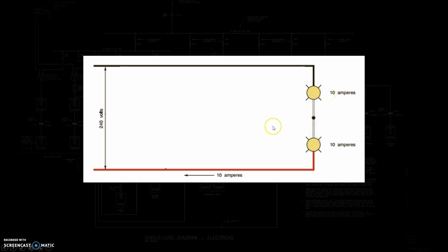There's no current on the neutral. And in fact, in this case, it's not even really doing anything. So in this sort of perfect scenario, theoretically, we've really constructed a series circuit. Now, we wouldn't wire things like this because, again, if somebody put a different light bulb in here, plug something else in, now we're not in balance. And that's going to create the scenario in your textbook where you lose a neutral, everything's out of whack.